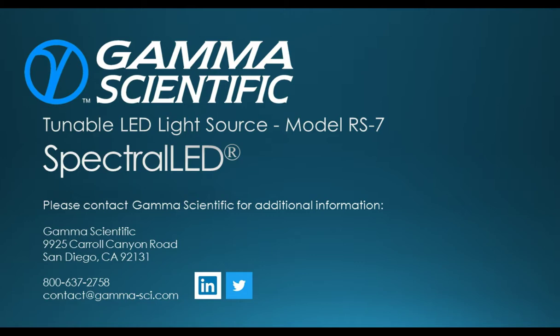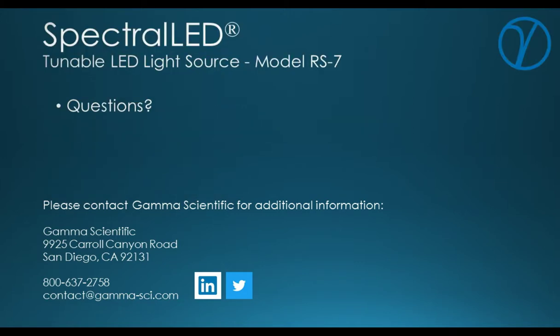Absolutely. So we're currently in development of a shortwave infrared unit. We are integrating an extended InGaAs photodiode feedback into that system and basically replacing all the visible channels with shortwave infrared channels. So that new device we expect will be available right around the beginning of the new year in 2018, and will essentially cover the shortwave infrared region with similar capabilities to what we've shown here in the visible and near IR.